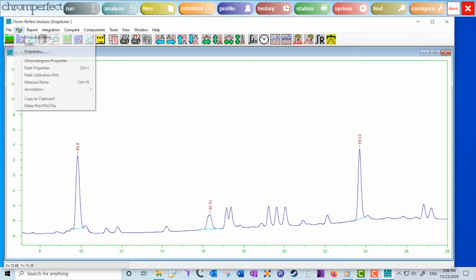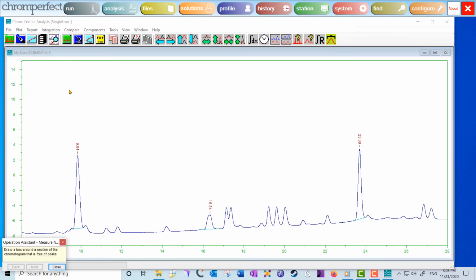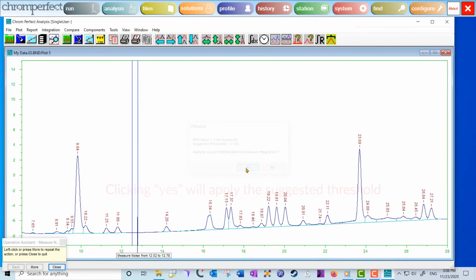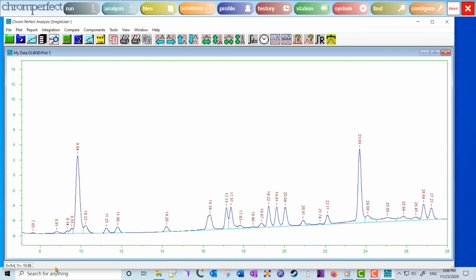Pull down the Plot menu again and choose Measure Noise. Use the mouse to define a region of the chromatogram that is free of peaks. Right-click to confirm. The software will report the noise level and suggest an appropriate threshold. You can record this value and enter it manually. Alternatively, you can select the option to use this setting and it will automatically be applied.